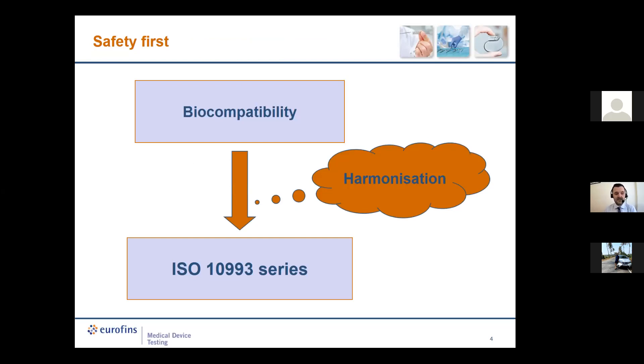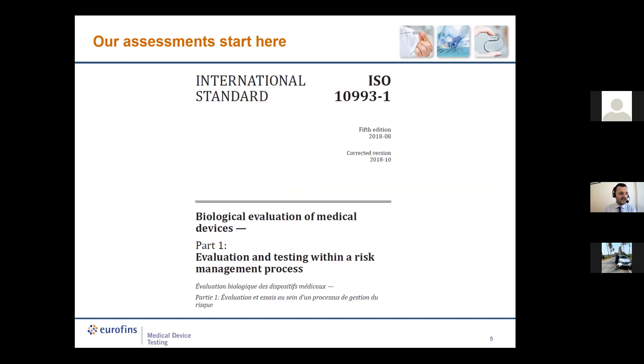The ISO 10993 series is developed by ISO TC-194 and in Europe by CEN TC-206. We now have 17 working groups at ISO level and one subcommittee working on those standards. So far more than 30 documents have been issued by this TC. ISO TC-194 is also taking care of clinical evaluation with a specific standard. At the moment no standard is harmonized under MDR, and the ISO 10993 series is not harmonized at all — we have to wait a little to have harmonized standards under MDR.